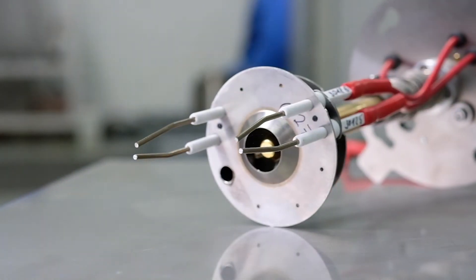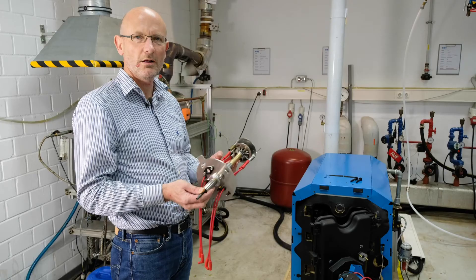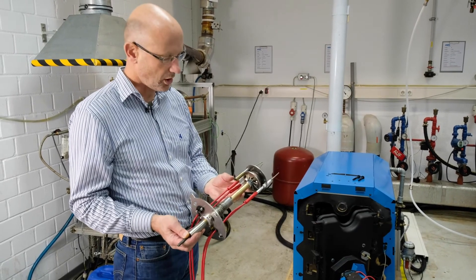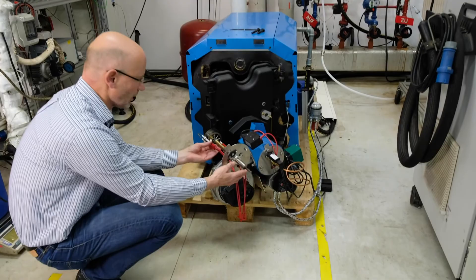The outcome of Residue to Heat is a new burner technology for condensing boilers — one that can handle pyrolysis oil or pyrolysis oil blends as an alternative for fossil fuels. That includes a new nozzle holder and a newly developed swirl generator with two spark plugs for igniting the FPBO, fitting the new burner.